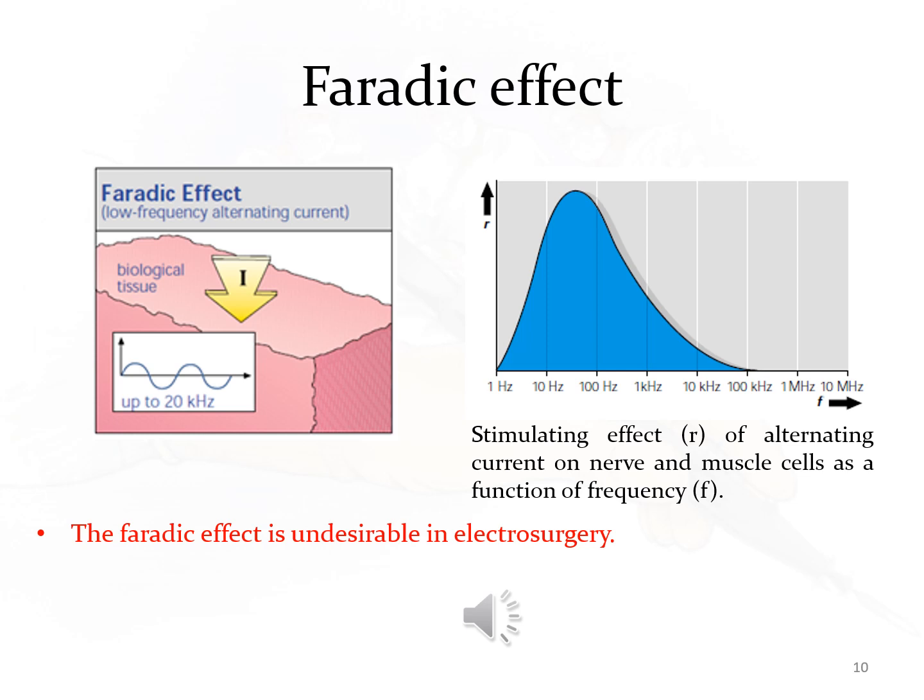At high frequency, this effect is undesirable, as muscle contractions are painful and possibly even dangerous for the patient and are hindrances for the surgeon. This stimulus effect peaks at frequencies between 10 and 100 Hz, as we can see in the figure.